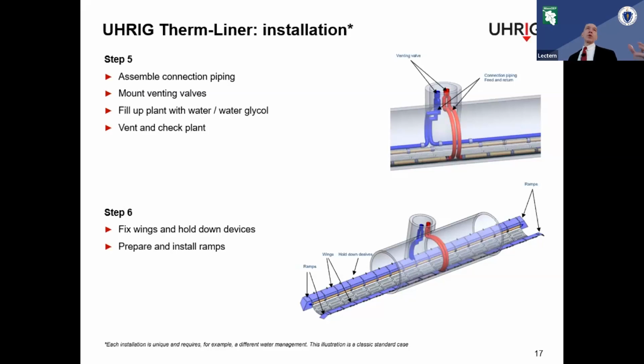Now there is a biofilm effect, right? When you install these systems, when they first go in, they actually overperform. The biofilm effect is part of our engineering process. We know what the biofilm is going to do from an energy reduction perspective, and we use that as part of our design criteria. So we design a system that, after it's been coated with biofilm, is going to perform at a certain energy capacity. When the system first goes in, it's normally overperforming.